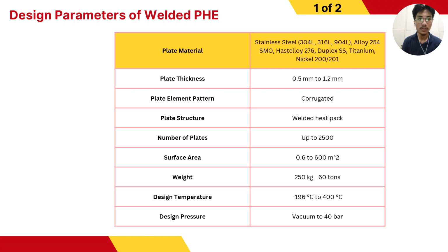So it is also dependent on a number of reasons or factors. This includes the working fluids or types of working fluids, as well as the working conditions, the temperatures and pressures. So when we have 1 megapascal pressure, the corresponding plate thickness is going to be 0.5 millimeters. And if it is more than 1 megapascal, 0.6 millimeters and above should be used. When it comes to too high a temperature, 1.2 millimeters is going to be used.